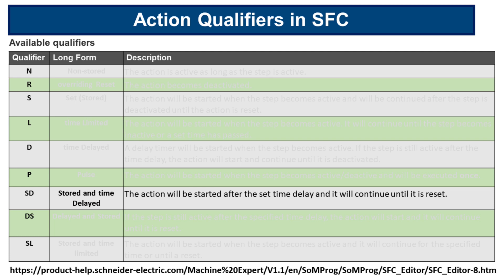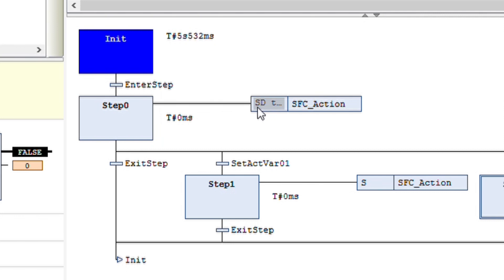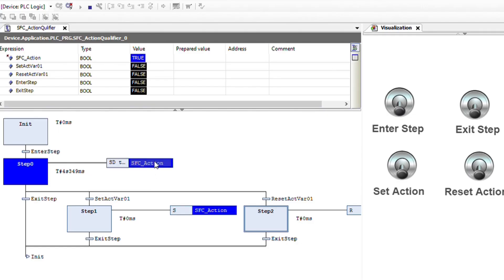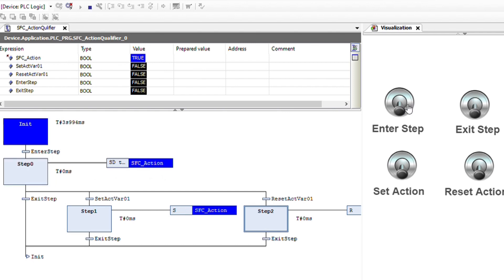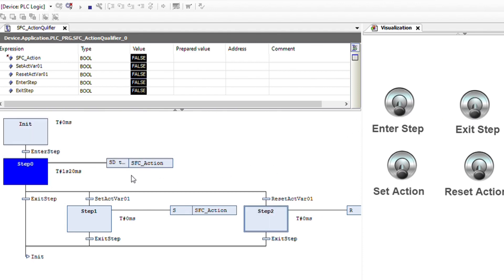The next action qualifier is SD, which stands for stored and time delayed. The action will be started after the set time delay and it will continue until it is reset. I have changed the action qualifier to SD with a time delay of 3 seconds. We start from init, enter the step, and after 3 seconds the action becomes true. If we exit from the step, the action will remain true until we reset it. If we enter again, after 3 seconds the action becomes true and will remain true until we reset the action.